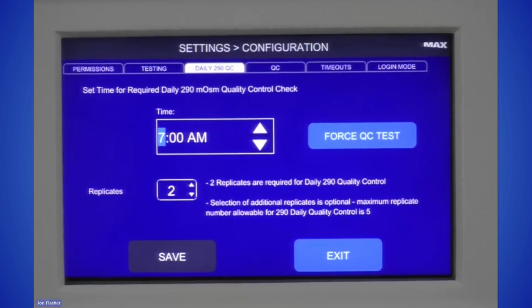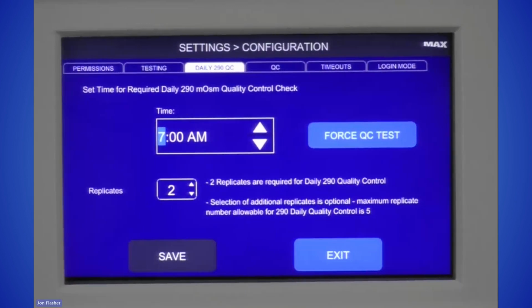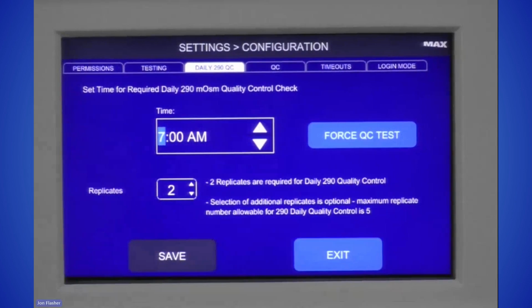Once you perform that QC, you're free to test for the next 24 hours. But if you schedule it for 7 a.m., for example, and you come in and try to run a sample at 7:05, the instrument will kindly remind you that you need to run your QC first. This is also where you can program a number of replicates as well. If you're outside of that time range, but you want to force the QC test anyways, you can hit this button on the screen as well.